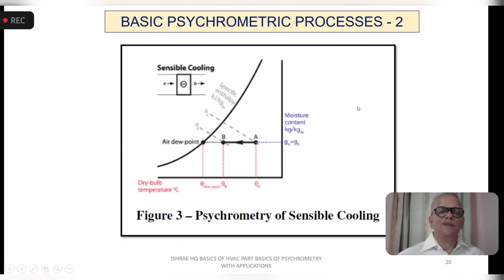The second process is sensible cooling, which is now going from point A, your starting point, to point B. There is no change in the moisture content. You are not dehumidifying or removing moisture; you are only removing sensible heat. So this is the horizontal line without changing moisture content, and this is the way it is shown as a process. This rectangle is the apparatus. The circle with the minus sign means you are removing heat, and that is the entering and that is the leaving air, and that is the delta T, or the temperature difference. That's the process of sensible cooling.